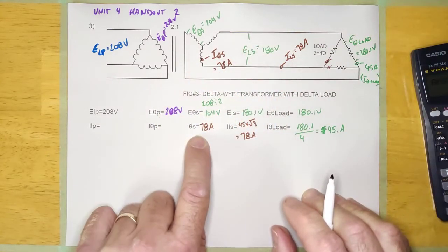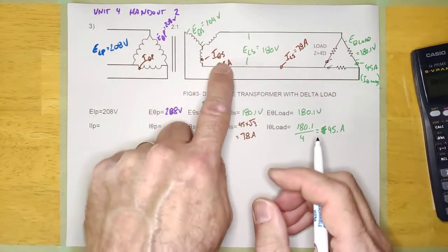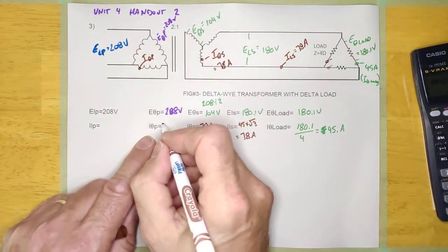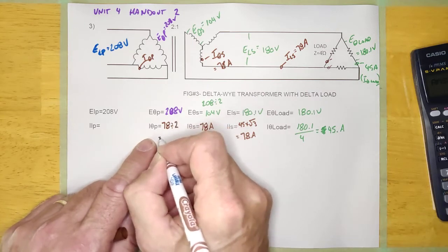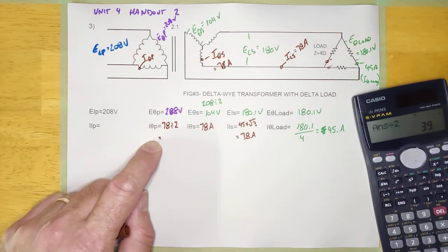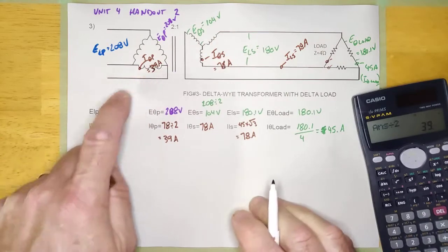I-phase primary — that would be the current here on the primary side of the transformer. It's going to go across the transformer from phase to phase at a ratio of 2 to 1. So this will be 78 divided by 2, which equals 39 amps. And that would be right here.